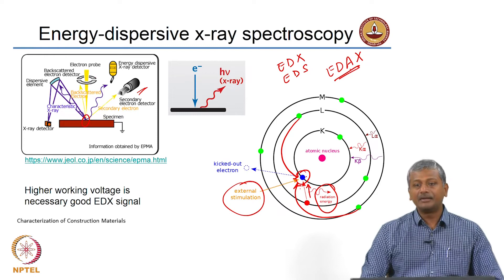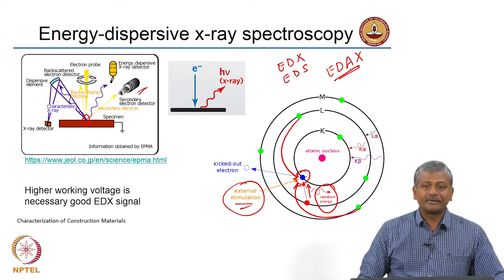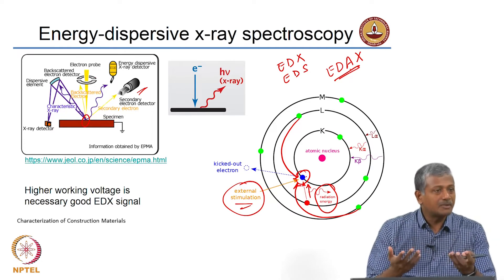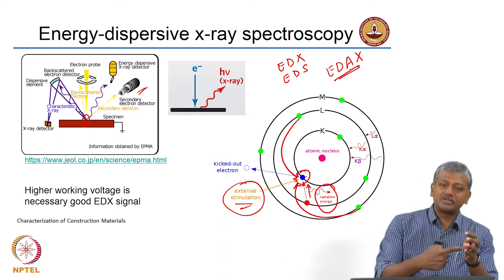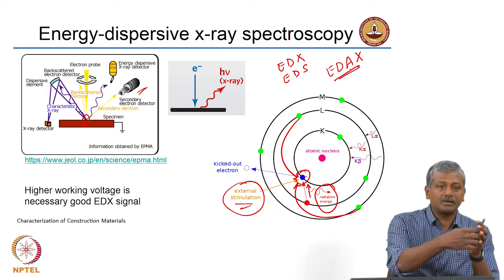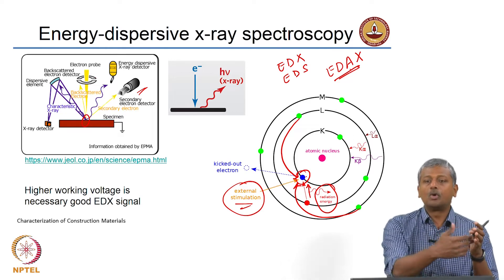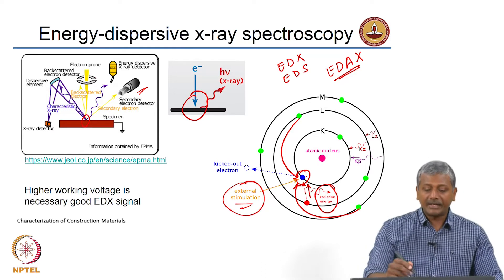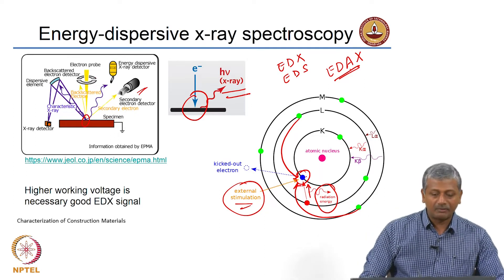This process is closely related to X-ray fluorescence — in XRF the external stimulation is by X-rays, while here it is by high-energy electrons. In fact, what happens inside an X-ray tube is essentially X-ray fluorescence: high-energy electrons accelerated through a potential difference hit the target metal and generate that metal's characteristic X-rays — copper generates copper X-rays, cobalt generates cobalt X-rays. Energy dispersive spectroscopy detects the X-rays fluoresced from sample atoms due to interaction with the electron beam.